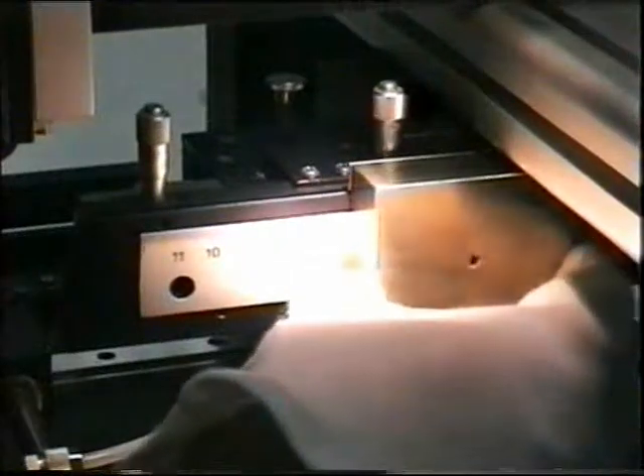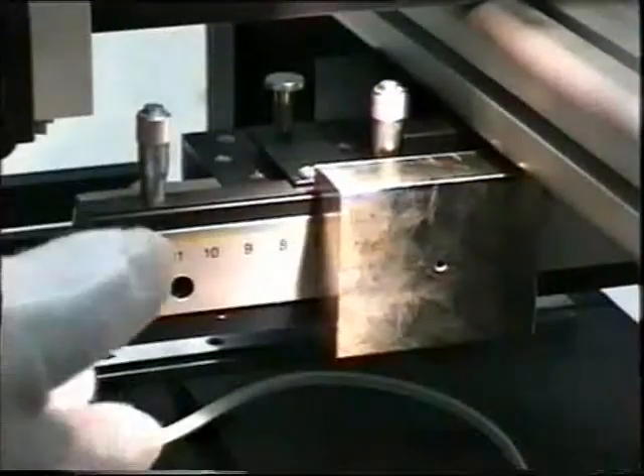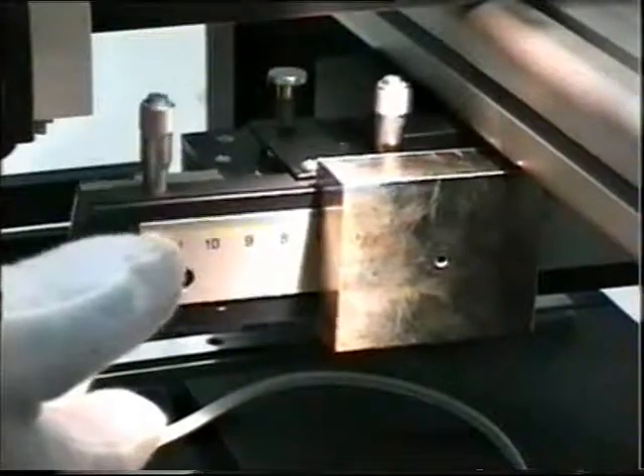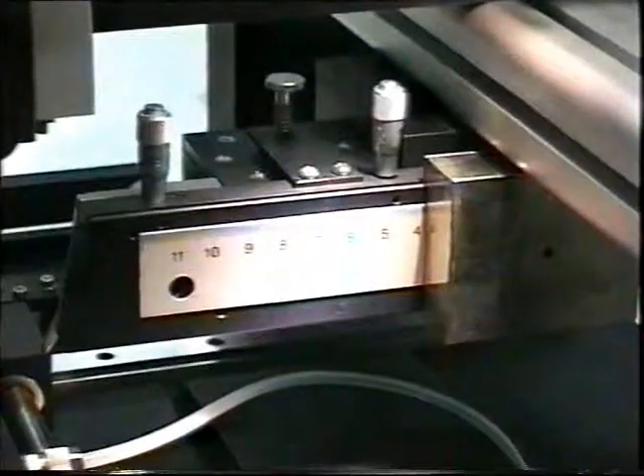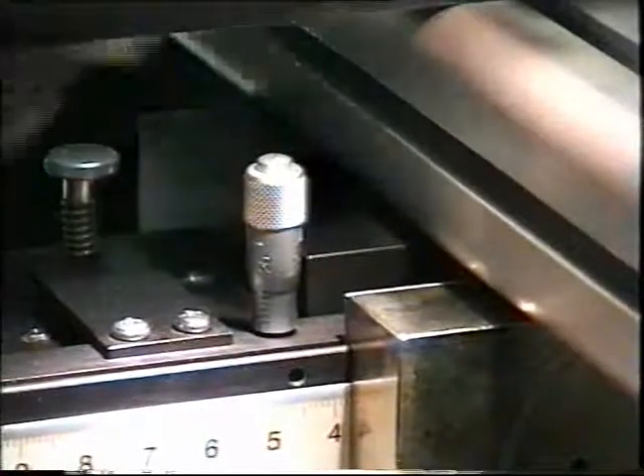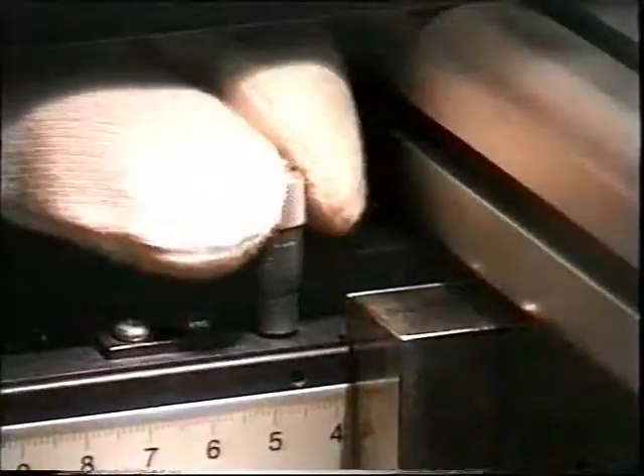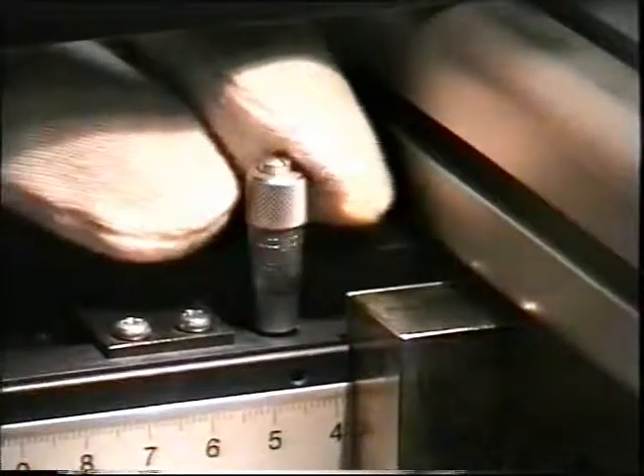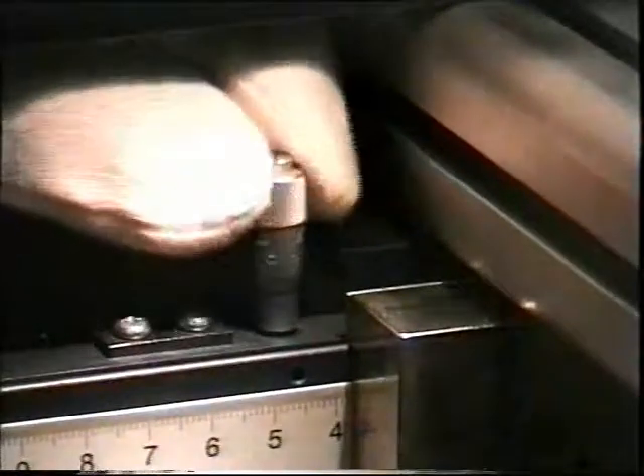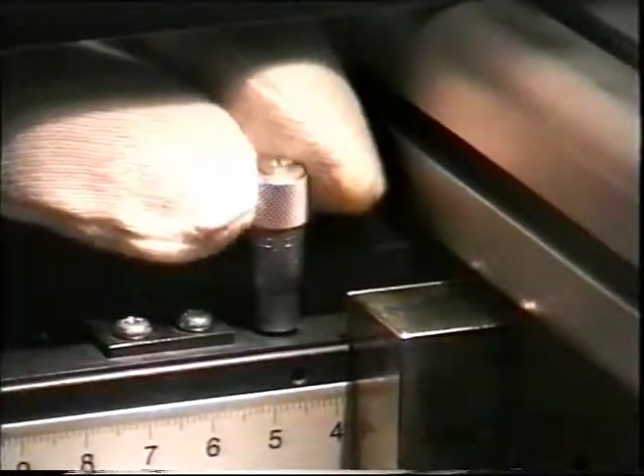The scribing force of the diamond tip can be adjusted from 0 to 300 grams, or from 150 to 500 grams. To process substrates of different thickness, the diamond tip position above the vacuum chuck is adjustable by a micrometer screw.